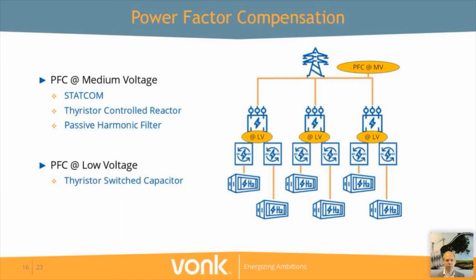The third commonly used approach to power factor compensation is a passive harmonic filter. We don't regard this as a very suitable solution for the electrolyzer application because it lacks dynamic behavior. And obviously the electrolyzer application has dynamic behavior. So it's not the one that we would suggest. However, it's supplemental to the former two, as in case you apply a passive harmonic filter, you can lower the amount of STATCOM or thyristor controlled reactor capacity that you need, and therefore have a cheaper overall solution.